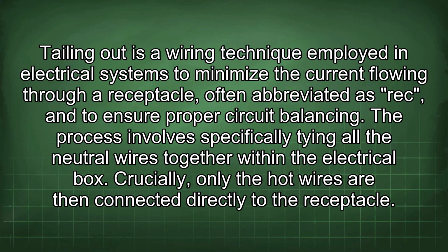Tailing out is a wiring technique employed in electrical systems to minimize the current flowing through a receptacle, often abbreviated as REC, and to ensure proper circuit balancing. The process involves specifically tying all the neutral wires together within the electrical box. Crucially, only the hot wires are then connected directly to the receptacle.